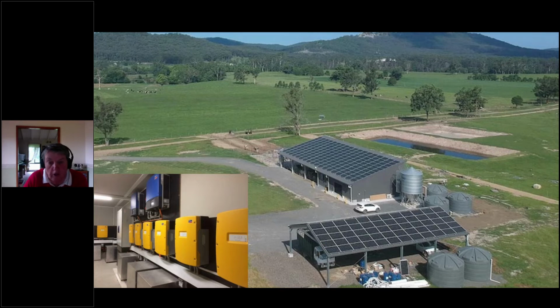Heating water is one of the largest consumers of power, and one of our system washes happens at 4 AM, and that often triggers generator usage. So we are now considering installing an additional hot water system to increase our hot water storage, and this would overcome that issue and would be far more cost effective than the installation of additional batteries.